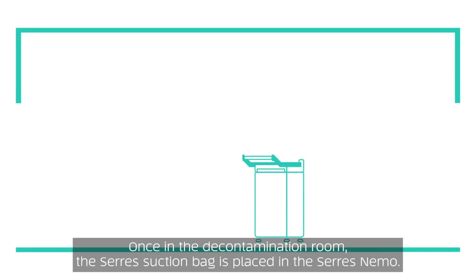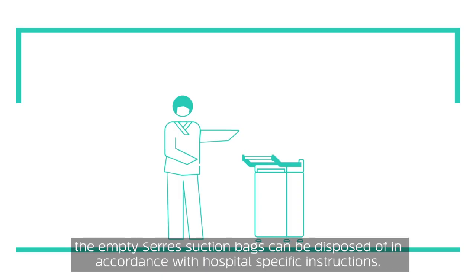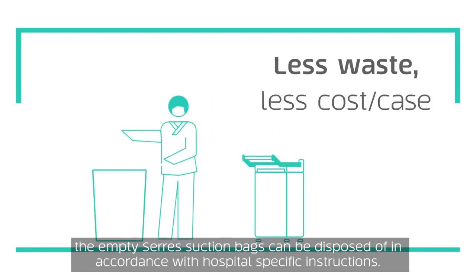Once in the decontamination room, the Serres suction bag is placed in the Serres Nemo. An automated 18-second emptying cycle is run. When the cycle is finished, the empty Serres suction bags can be disposed of in accordance with hospital-specific instructions.